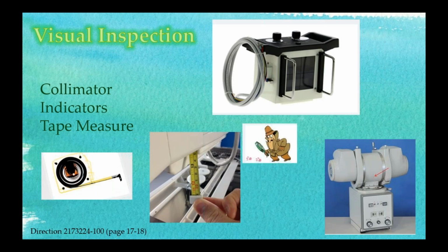The tape measure, if you look at a tape measure of an x-ray system, it's not going to start at 0 and go through 1, whatever. It's going to start at 10 or 11. Why? Because we have to make up this distance between where the spot is and the bottom of the collimator. So the tape measure has to be cut off to make up for that. You might see that one again.